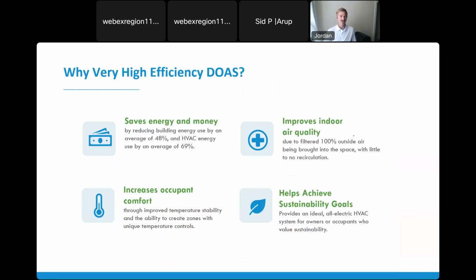Outside of just the energy use, with these systems we measured a number of different indoor air quality metrics. We followed the thermal comfort from the occupant standpoint very closely. We did a lot of surveys before and after, post-occupancy surveys. And what we found is that the indoor air quality from these systems improved greatly. The occupant thermal comfort was far superior to the previous systems, which were typically either packaged gas rooftop units or VAV with reheat, by far the most common. And then these systems, being all electric, ultra low EUI systems, helped significantly decrease their carbon footprint. So very important to some of the building owners in terms of their sustainability goals.